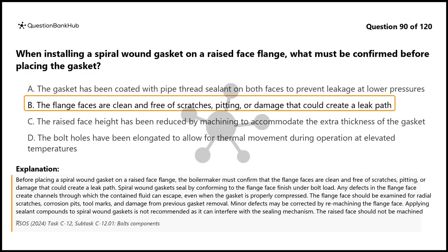Any defects in the flange face create channels through which the contained fluid can escape, even when the gasket is properly compressed. The flange face should be examined for radial scratches, corrosion pits, tool marks, and damage from previous gasket removal. Minor defects may be corrected by remachining the flange face. Applying sealant compounds to spiral wound gaskets is not recommended as it can interfere with the sealing mechanism. The raised face should not be machined down, and bolt holes should not be modified.